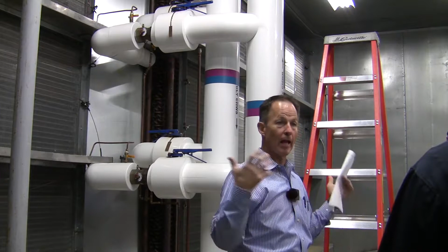So what happened? Okay, so the graphics got built by guys that never got into this area, right? And the temperature sensor looks right. Maybe it's wintertime, I'm 55 here, I'm 55 there, I got no heat on, or everything looks good, and so the sensor was never physically verified. The installer put it on the wrong side, maybe it was a coordination issue, who knows. But it's actually needed though because of where the coils are, it's probably better there. And maybe what happened is the decision was made to put it there because it was better, but the guys that did the graphics didn't get that info, so it didn't get put right. So we'll fix the graphics, but that's one little thing - when you find something weird on a graphic you're working with, let us know.